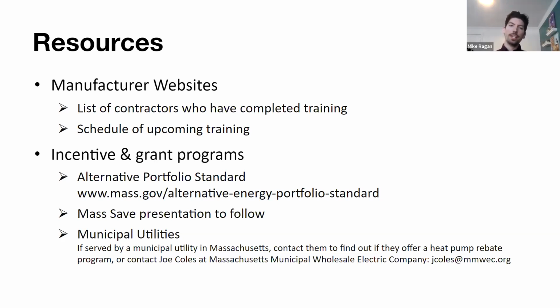Yeah, for retrofitting existing hydronic systems, that would require a bit more robust of an analysis as to how the existing system is currently laid out and what the possibilities are. Air to water, it's a bit more nuanced of an application. Just speaking from my own personal experience with an air to water project I'm working on right now, there are a lot of questions to consider here in terms of what's being delivered. So I'm working on a project where we have an air to water hydronic system that is going to be controlling a condenser water loop. So the VRF system is ensuring that a 90-degree water loop is running throughout the building at all times.